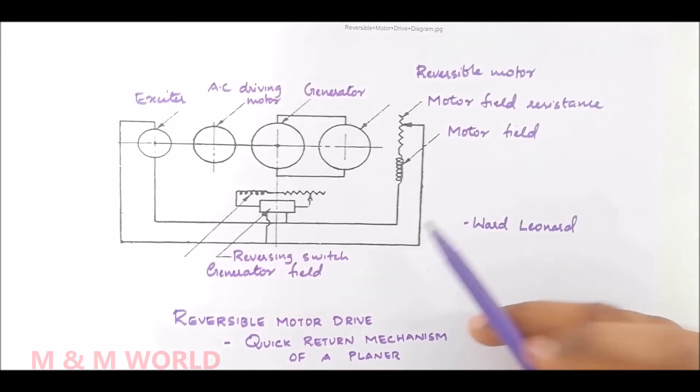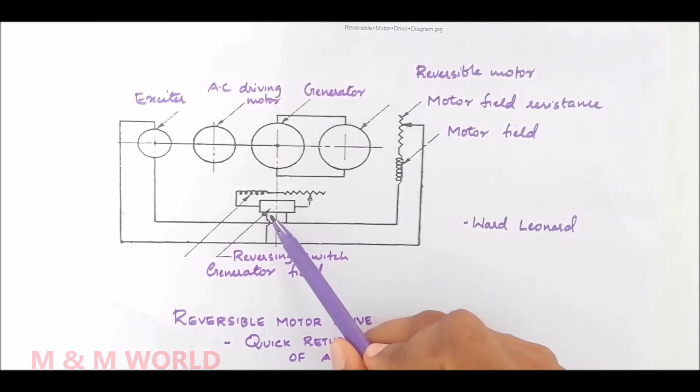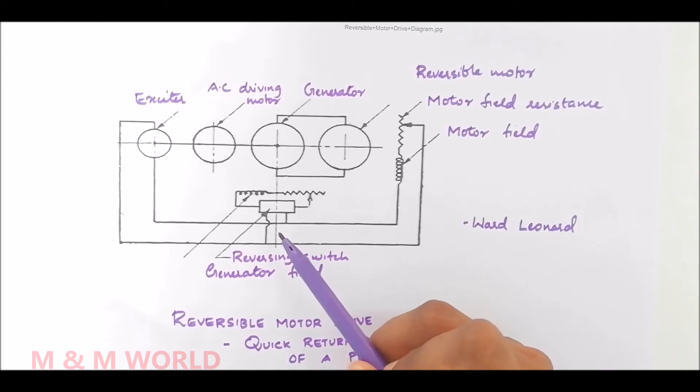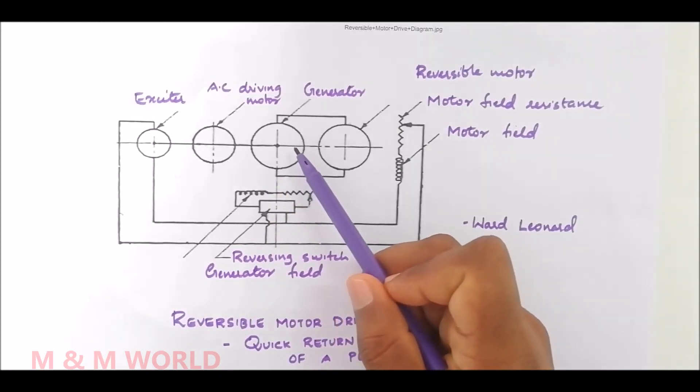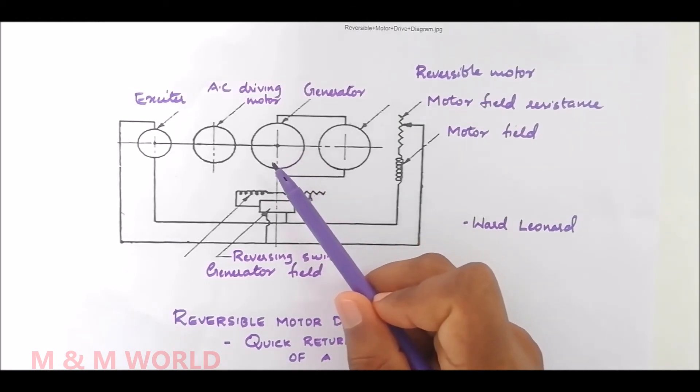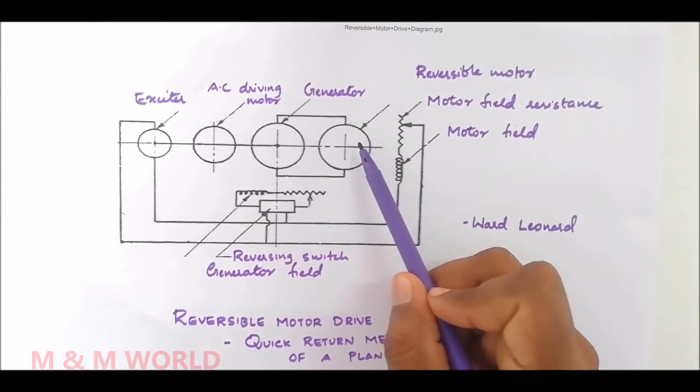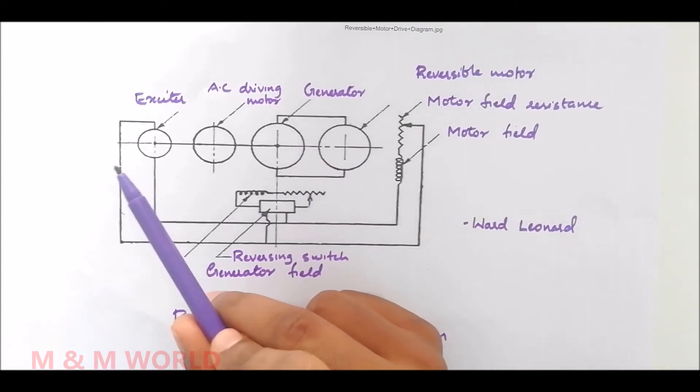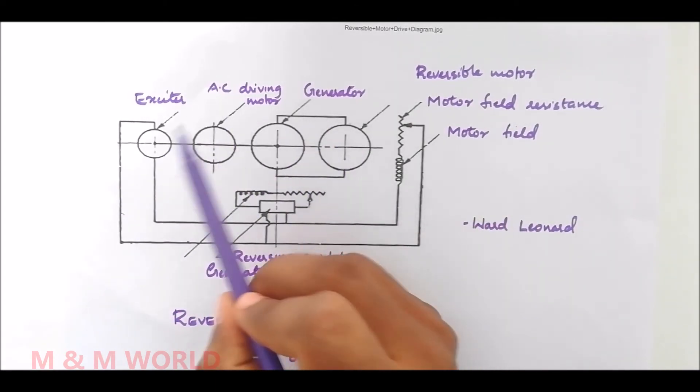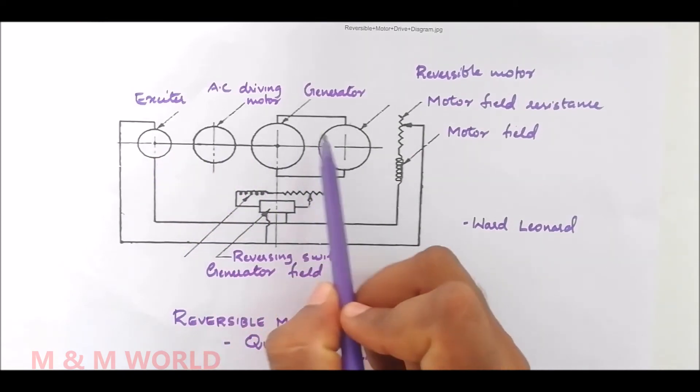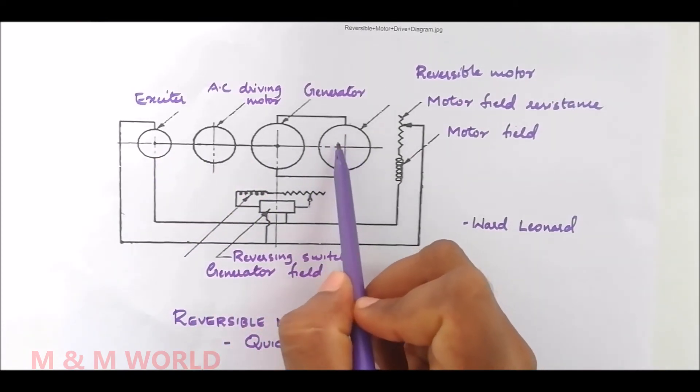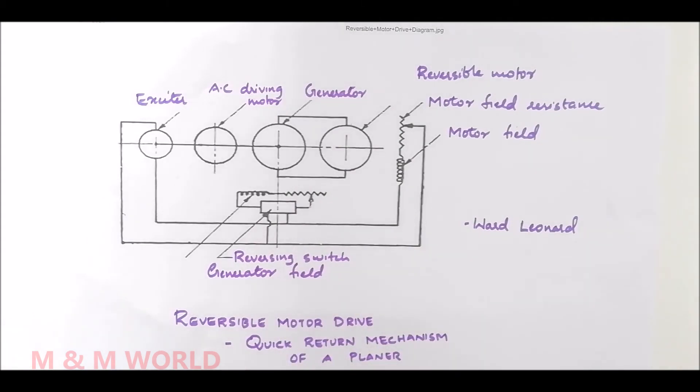At the end of the stroke, a trip dog operates the reversing switch, which reverses the field current in the generator so that the polarity of the armature current in the reversible motor is reversed, while the motor field current continues to receive current from the exciter at the same polarity.